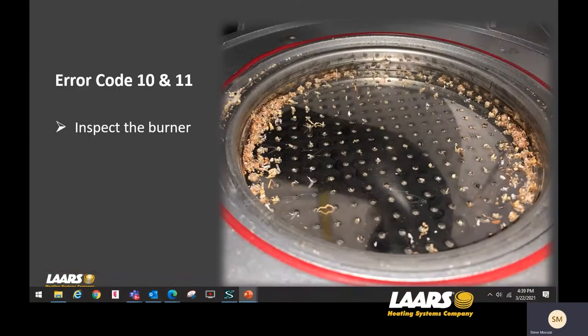We've talked about gas pressure and checking and cleaning the igniter. Also consider inspecting your burner. Here we're showing an image of wood chips — we've seen all kinds of things on top of burners, most commonly PVC shavings from the installation where someone's cutting PVC pipe with a sawzall. Those shavings get pulled into the blower and spit into the burner, plugging it up. Error codes 10 and 11 can also be caused by a dirty burner.